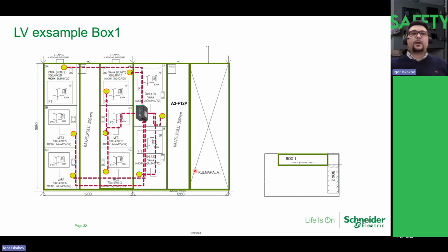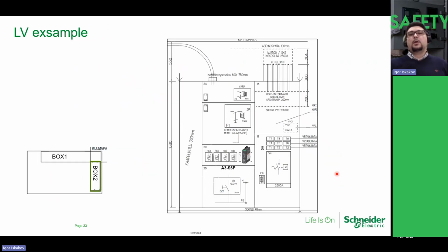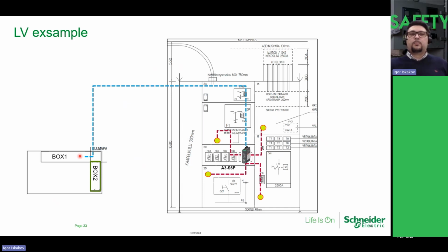The tripping contact can provide a trip on the main breaker. But in case we have, for example, 2 switchgear situated in the same room, we can connect a second unit with the second switchgear by a modular cable, which also provides the power supply to the second unit. Here in this example you see the second compartment, where we find the place to situate our second unit, and we situate our sensors. It will also be possible to build 1 system across the 2 switchgears with some selectivity, for safety and, how to say, less tripping on the low voltage switchgear.